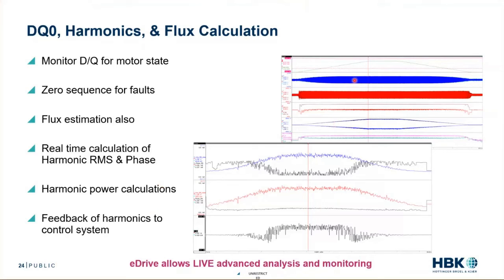So up here I've got my DQ0, my D-axis currents, my D-axis voltages, my fluxes, my harmonics. This is all to say, if your FEA guys, your CAE guys have said I think my failure modes are going to be at a certain flux level and we're going to see an increase in the harmonics, you can plug those in and have those monitoring live. You can trigger on those values, watch them, and see if they exceed a threshold. The eDrive system allows live advanced analysis and monitoring so that you can trigger on all these values.